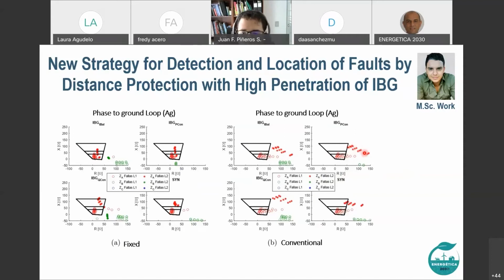But then a possible solution is exactly to improve these algorithms, to make modifications to them, and he is working on that. These are faults we cannot see, but with a modification, this is an example for a single-phase-to-ground fault, before you were not able to see it, and then with the modification you can see it. Of course, this has to be tested properly, but it's important because, I will tell you again, if you are not able to provide a good backup for external failures, the problem is, remember, you have your low voltage ride-through timing, and if you don't care about it, then you can lose very big quantities of inverter-based generation.